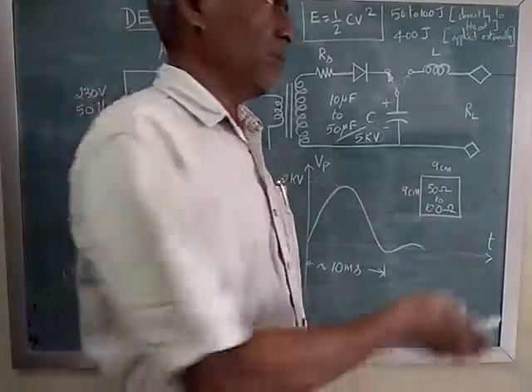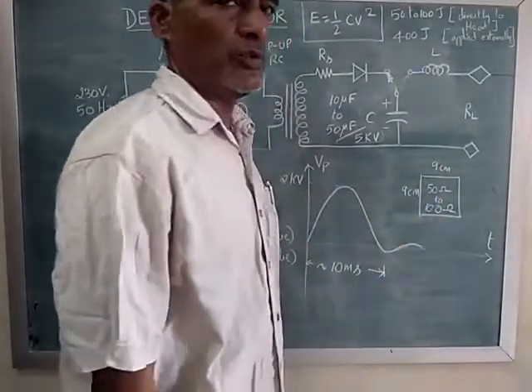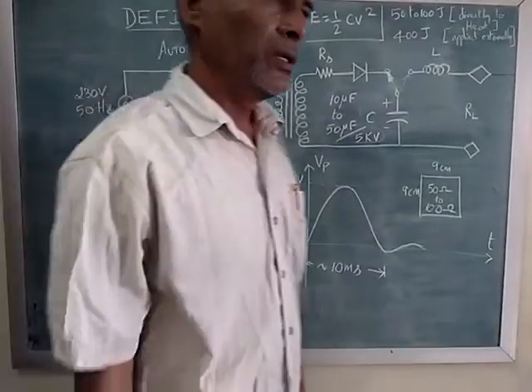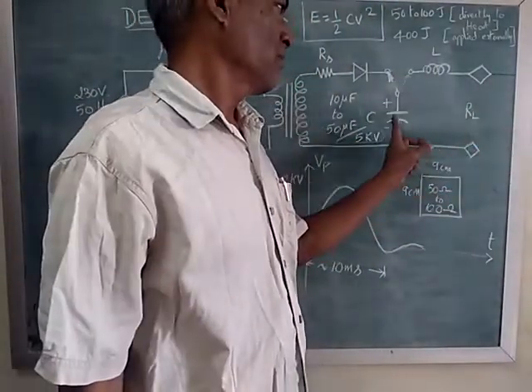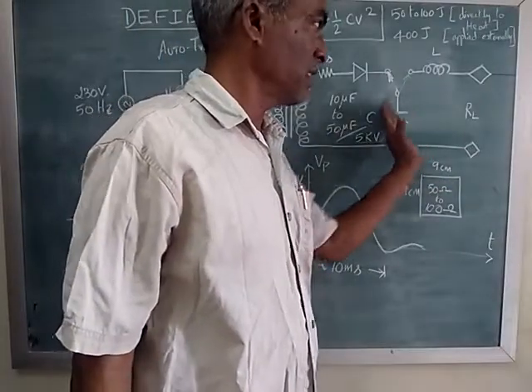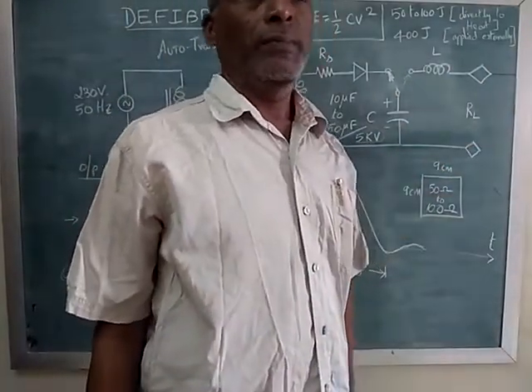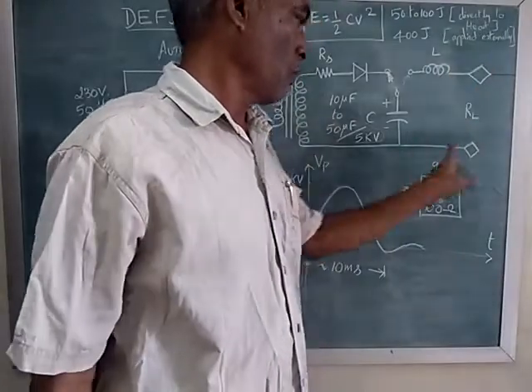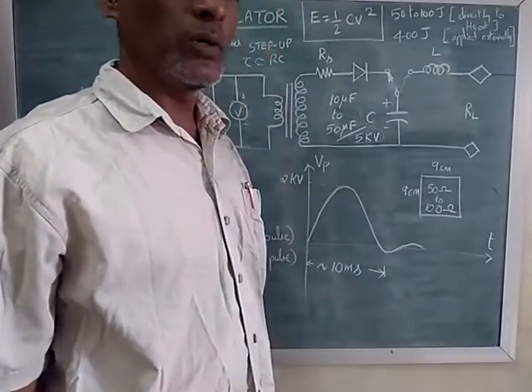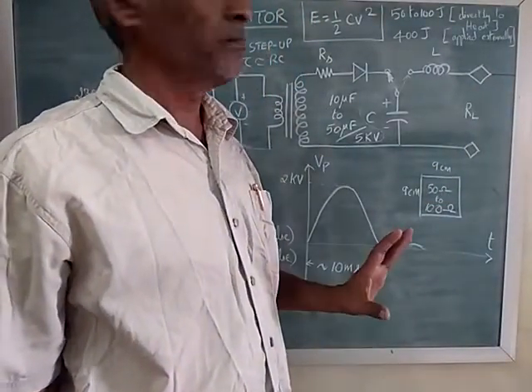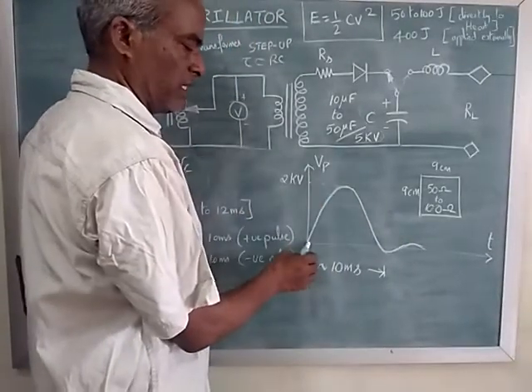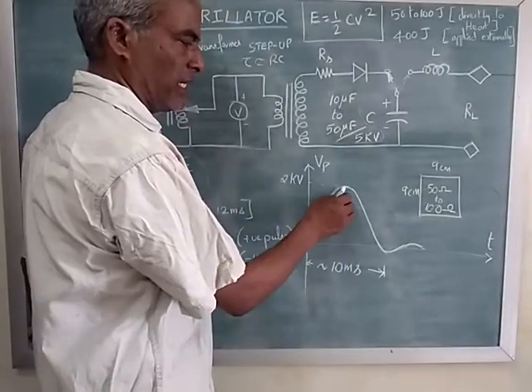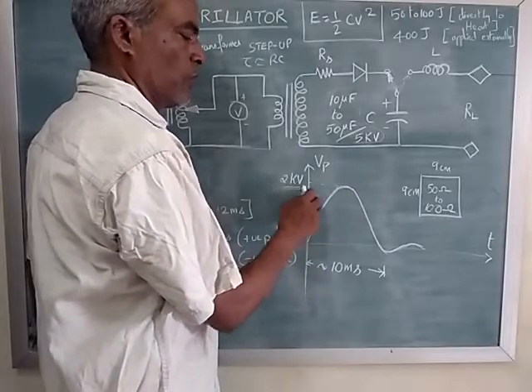And there is a key, this switch, usually it will be kept at the foot. So when you press, it connects here and discharges. This voltage across the capacitor is discharged through the patient and to the ground. Now you must know what is the waveform.